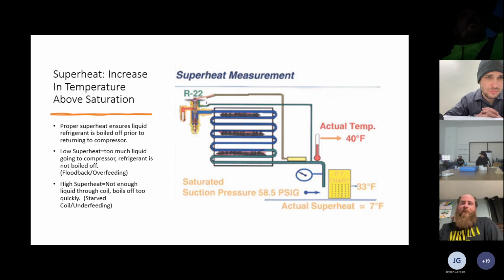If EPR is too low. So one thing Cody said, rack system, non-condensables. EPR is too open, if it's running at a colder temperature than it needs to be. What else do you guys got?